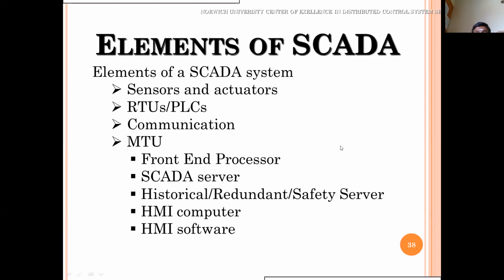That push button will have some variable, and that variable will be tagged to the push button. Whenever you change the status of the push button, it will be indicated in the SCADA. You can also vary the push button status in the SCADA, and that will be reflected in the PLC. Not only in the PLC, it also happens in real time, and the process will be affected. So what is happening in the SCADA can be reflected in real time.